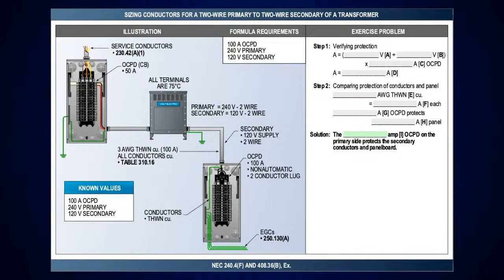Yeah, and then we're showing you here where you go to a panel board and you're protecting the panel board. Oh, gotcha. Okay. And this just gives you something to look at, because sometimes they throw this on the test, to protect the panel board. So you just need that primary and secondary, then get the amperage upstream. In this case, it's a 50 amp. By the time you do it, we actually gave you the answer in the illustration. It's 100 amp, but we wanted you to know how we determine that, and this is how you do the calculation. So it's just a quick calculation for everybody to understand how to put it together.